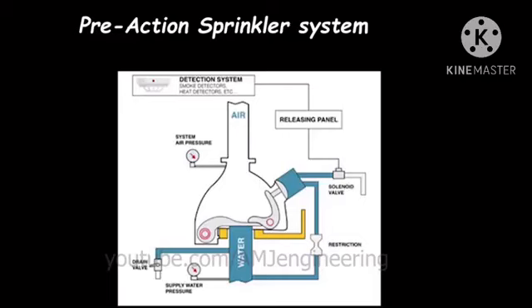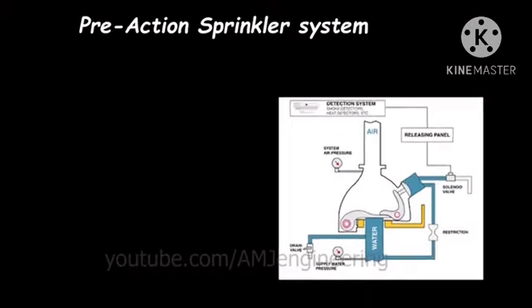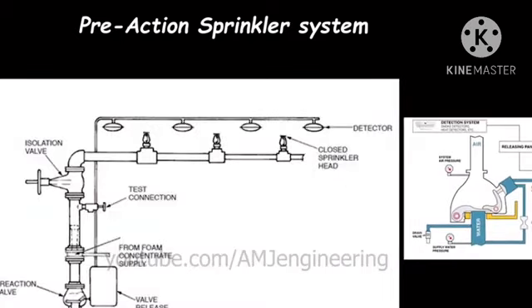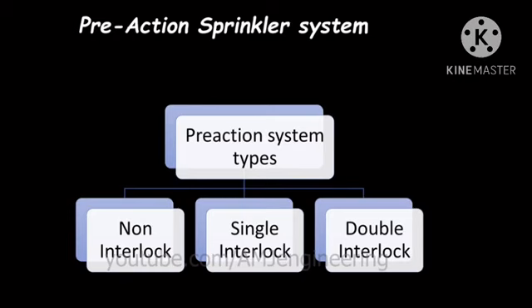Pre-action system. A pre-action type sprinkler system employs the basic concept of a dry pipe system in that the sprinklers are closed and water is not normally contained within the pipes. One difference, however, is how water is admitted to the system. Water introduction into the system's piping is initiated by opening of a normally closed, mechanically latched valve known as a pre-action valve. Means of operating the pre-action valve depends on which of the 3 types of pre-action systems, non-interlock, single interlock or double interlock, is installed.